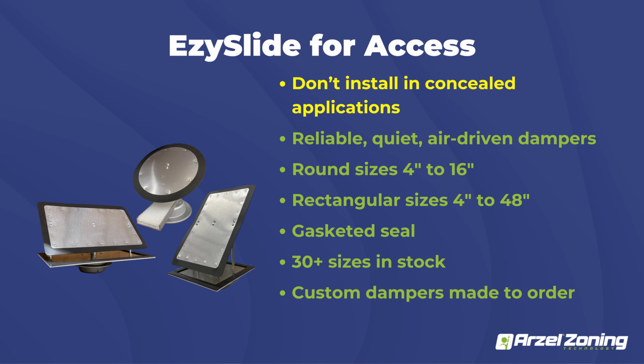All of these dampers are going to have a 3/4-inch gasketed seal on them. So these are 100% closure on the dampers. They don't allow for any kind of bleed by. But if you ever have a need, maybe you've got a smaller zone and you don't want it always to close off completely, you want to bleed off a little bit of your static pressure into an opposing area of the home, you can do one of two things. You can either trim the gasket material, which works really well, or you can just order the next size down.